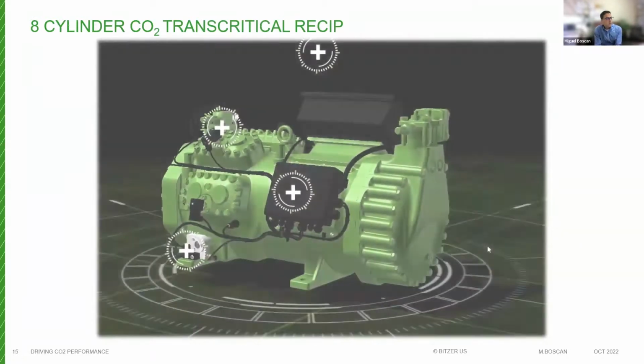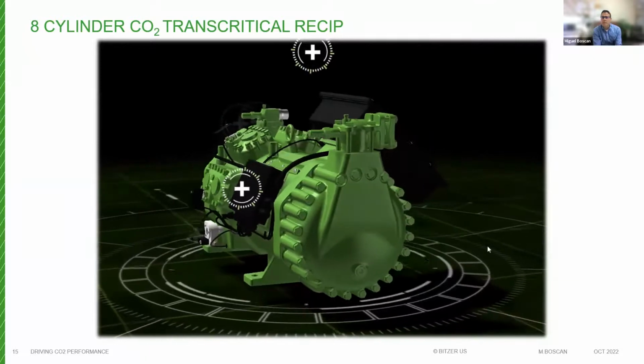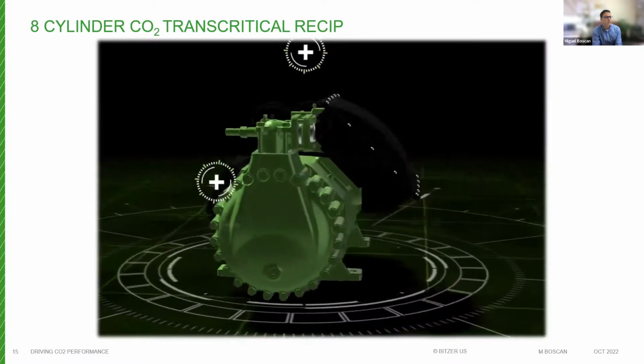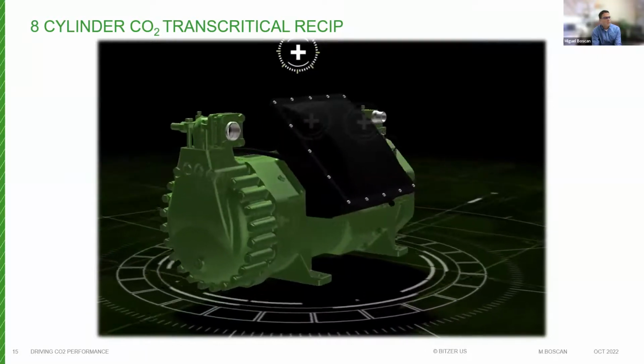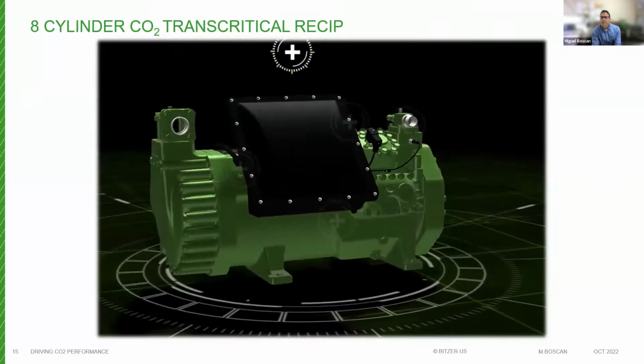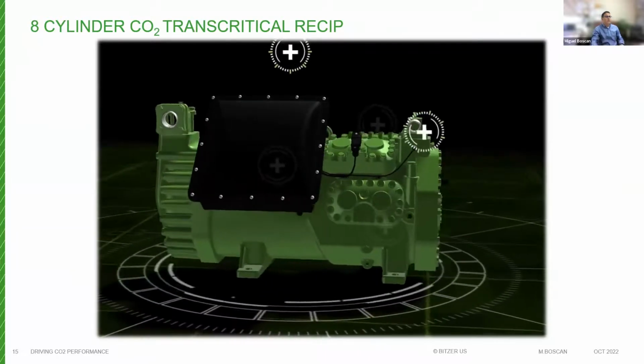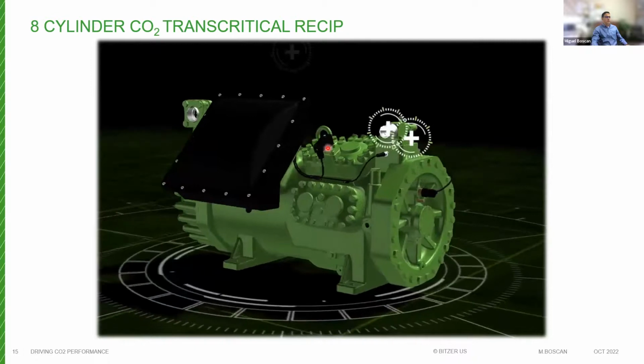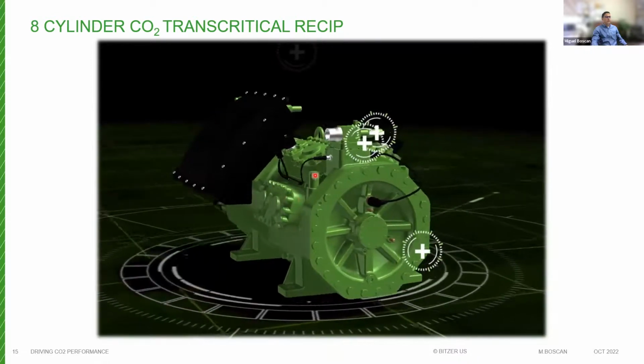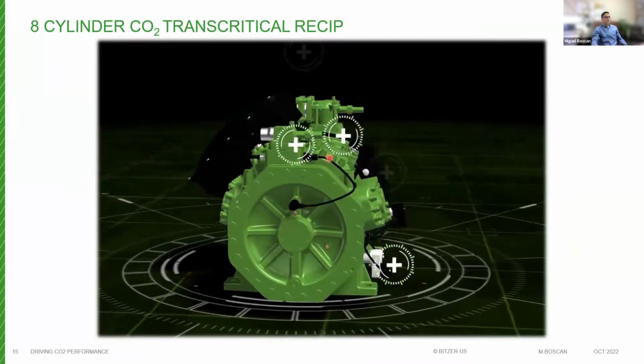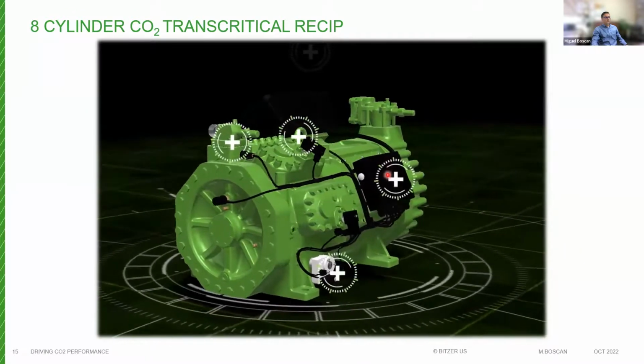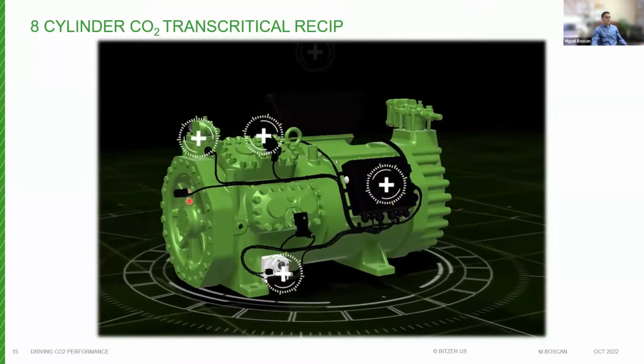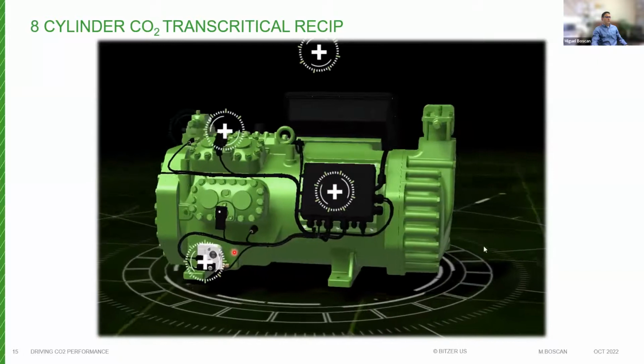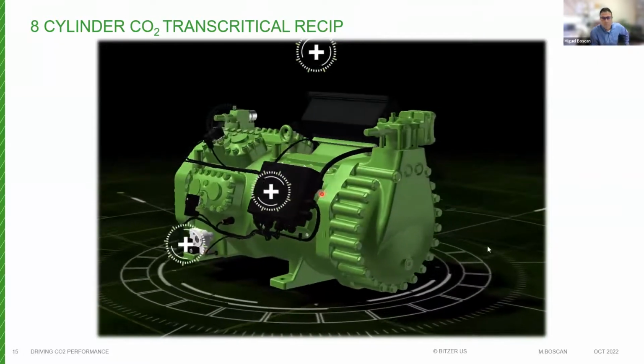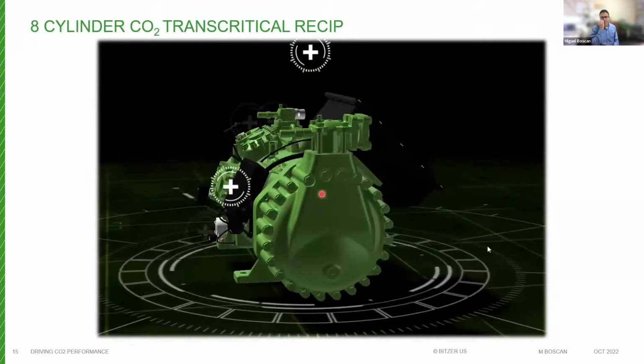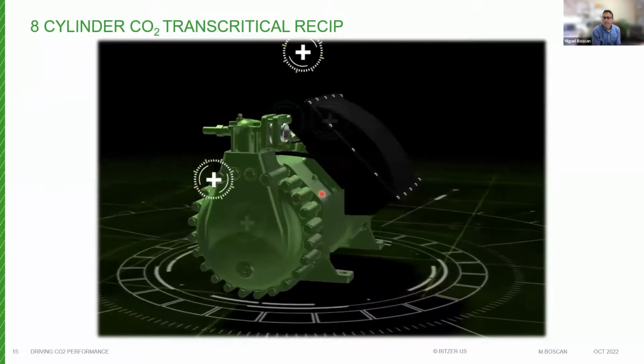Next, the last product, which I didn't mention in the agenda, is the 8-cylinder transcritical CO2 compressor. You can see on the screen the design of the 8-cylinder compressor. It's going to be fully integrated with a CMRC. Right here you can see the unloaders on 3 of the cylinder heads; the 4th one does not have that. You have pressure and temperature transducers and sensors that connect back to the CMRC, the Delta P oil pressure sensor, and oil level monitoring, all connected back to the CMRC for monitoring and functioning of the components attached directly to the compressor.